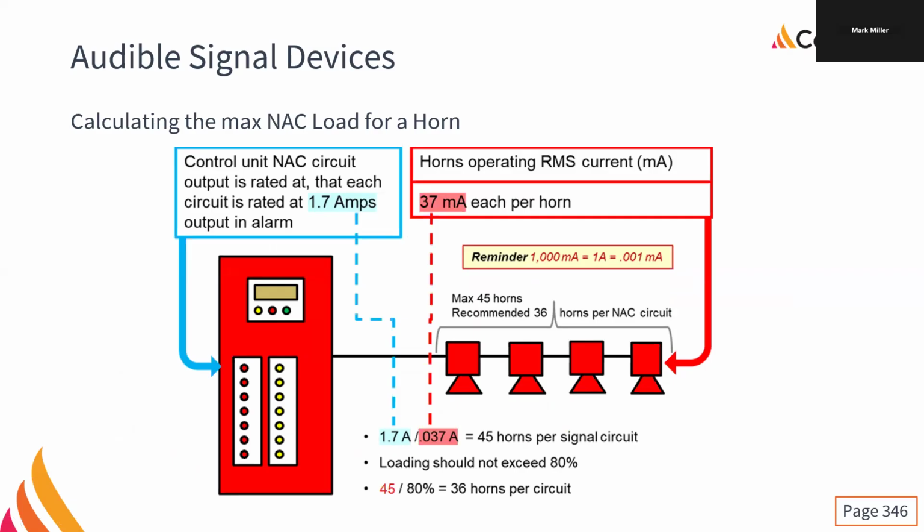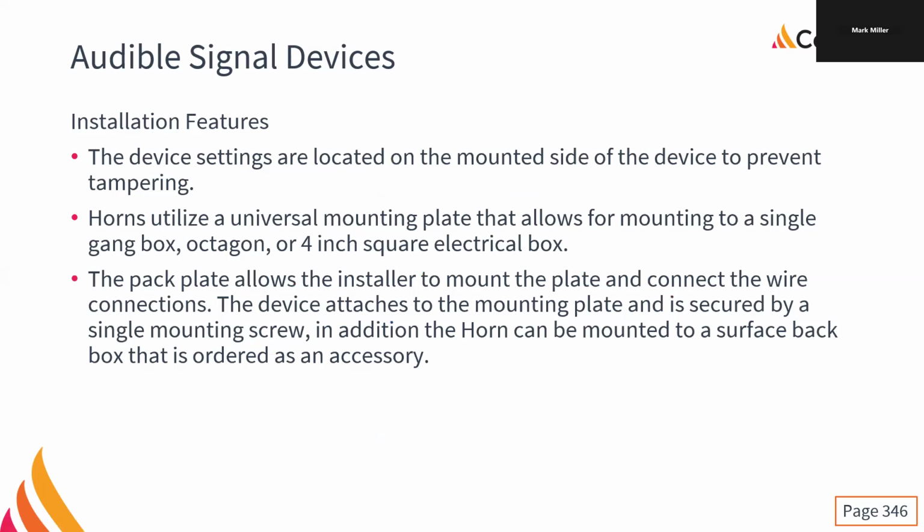If you start to put too many devices onto the circuit, you're getting into your whole eggs in one basket thing. But also, from a troubleshooting standpoint, it can be a little bit difficult if you're trying to troubleshoot and you have to go across 6 floors. It can be really annoying. So keeping it a little bit limited is probably a good thing.